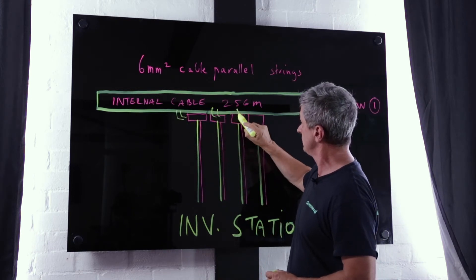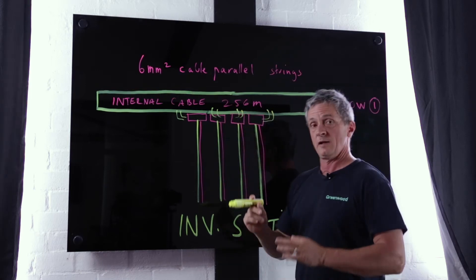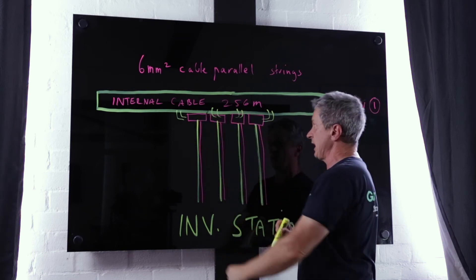We've obviously reduced our long cable run. Remember that cable run all the way to inverter station is 133 meters.